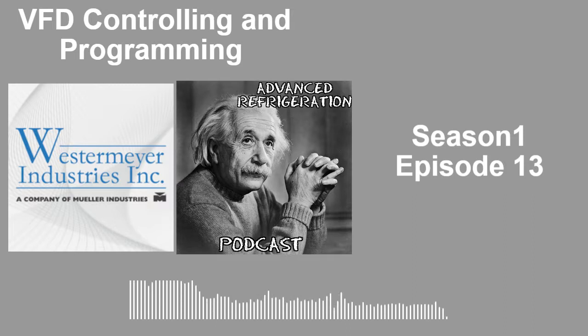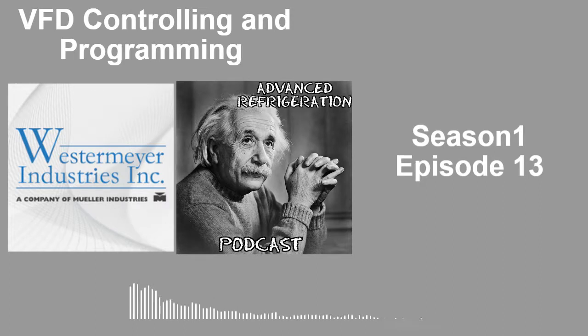So play with your settings depending on what you have in order to make this work properly. Otherwise, you could end up with a machine gun, just constantly cycling contactors on and off. In a cold weather application, you pretty much need VSS Combined, the variable speed control along with fan cycling. And in an area like where Brett is, you can get a long way with just variable speed probably most of the time, except for when Texas froze over.